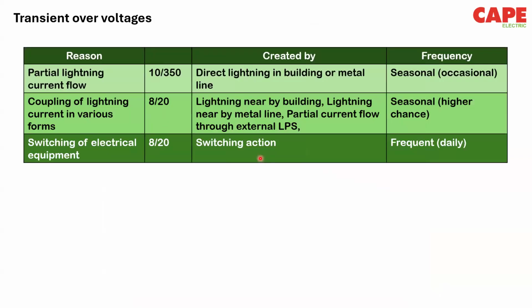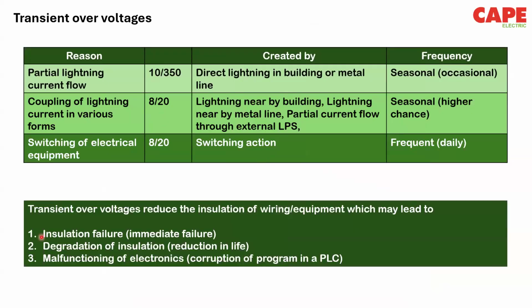So what happens when your SPDs are not there, or what happens during a lightning strike? Basically, you can have an insulation failure or degradation of your insulation. So there is a lightning strike, but you don't see an immediate failure in your system. But what happens is your insulation is stressed and there is a small degradation. So over a period of time, maybe after 5-6 days, maybe 10 days, or maybe in a few months, the insulation is stressed, and then you can have a fire and all these things. And then again, your electronics will be destroyed.